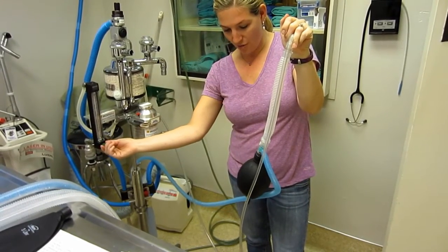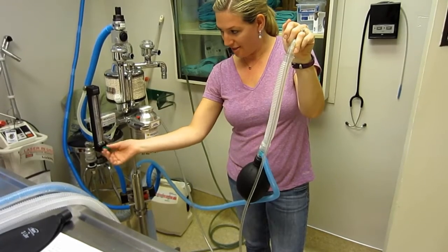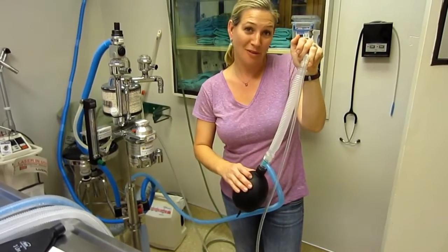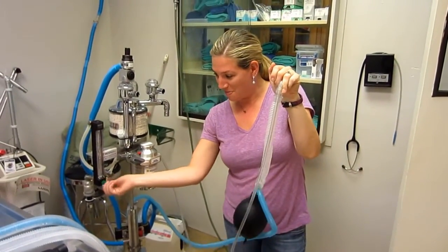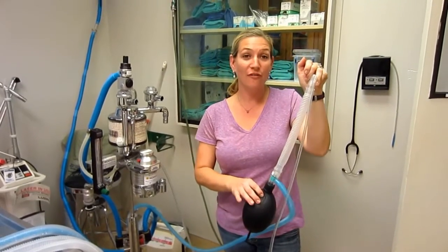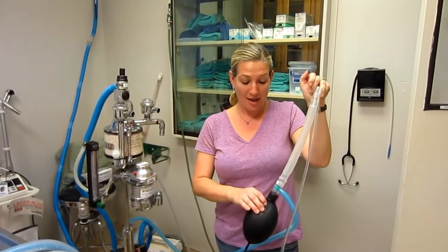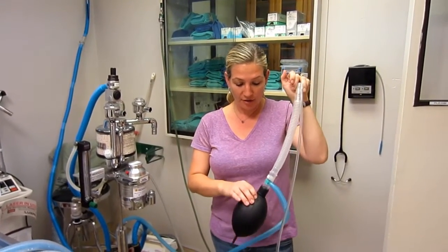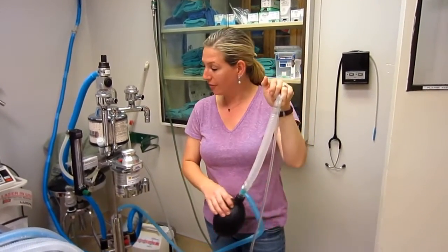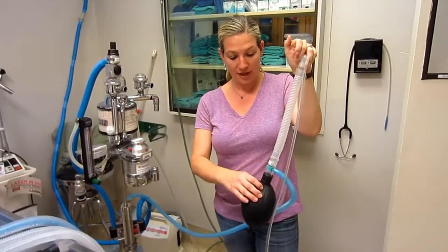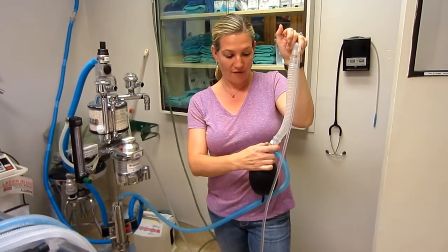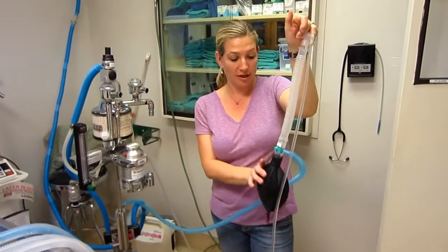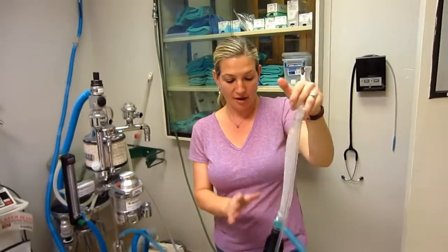And then I'm going to hold it for 10 seconds. And this actually has a hole in it, so I'm using faulty equipment at my hospital. If it didn't have a hole, you would hold it for 10 seconds. As it is holding there, you count 10 seconds, you make sure that it's not deflating, everything's fine. When you see that's fine, you open this valve up because you want to make sure that that exhaust is working as well, and you get that going.